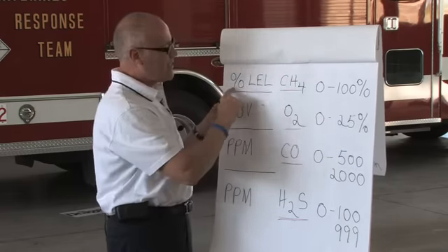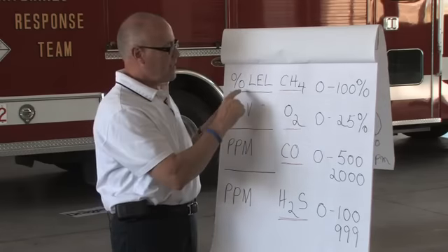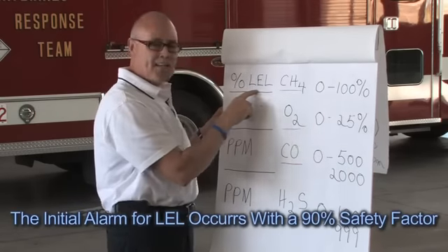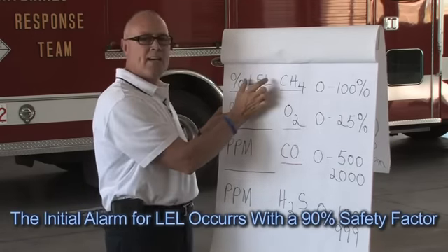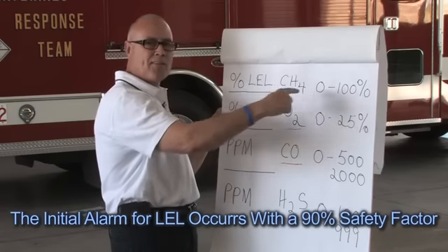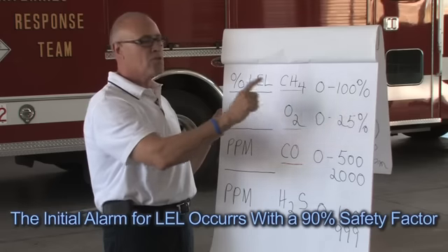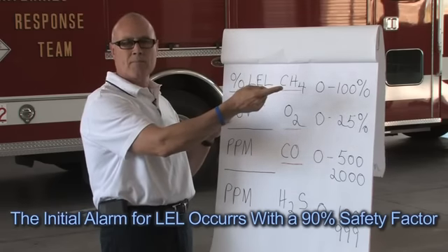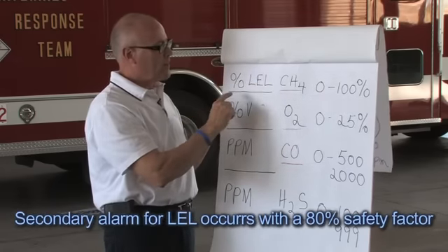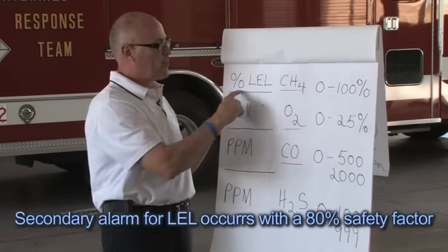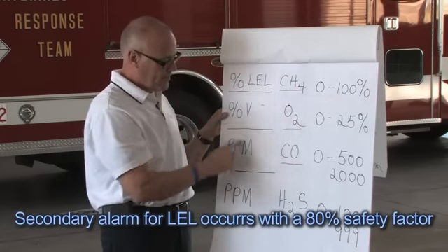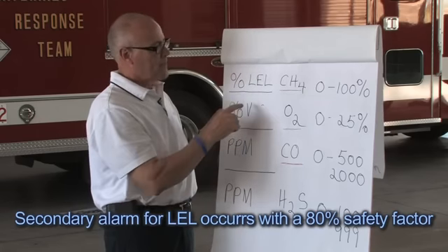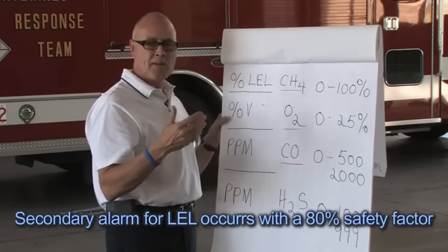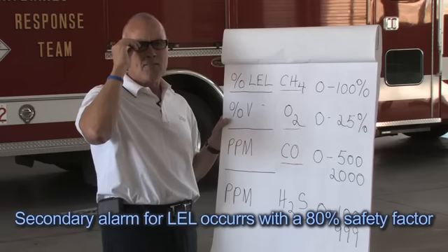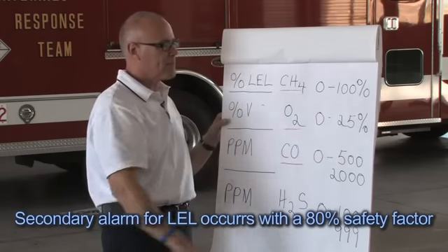The whole idea of these instruments is to alarm you at 10% of the LEL, which gives you a 90% safety factor to the explosion point. Okay? And there's also a secondary alarm that's also on this scale, and that's also true with these three scales, which is a more severe alarm. That would be 20% of the LEL, giving you an 80% safety factor.